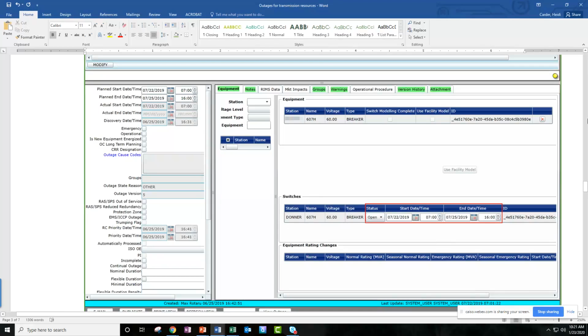Again, that's going to impact the power flow, impact your electrically connected resources, and so forth. So very important that we have those switches modeled correctly. And a lot of times when we find issues, it might be a switch or two that were added that maybe shouldn't have, wasn't actually part of the switching order associated with the actual field work.